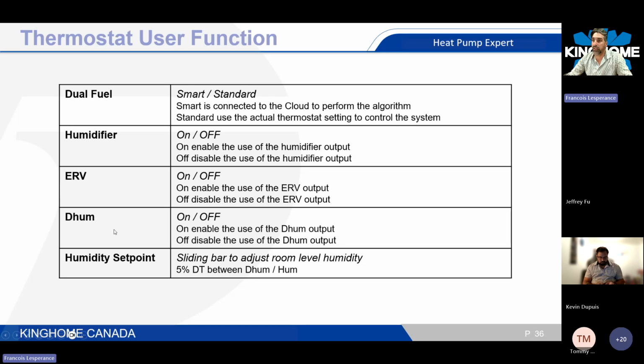Humidifier, ERV, and dehumidifier are some options that you can enable or disable with the on-off option. And you do have a humidity set point. This is a sliding bar that you can adjust to the desired room humidity level inside the house. Also, there's a 5% differential between dehumidifying and humidifying. So basically, there's a dead band of 5%.